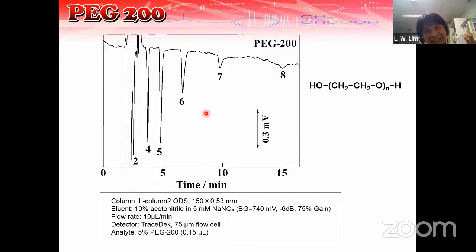So in this case, you have to find out what is the problem. And most of the time, you can solve the problem by washing your column, yeah? Because the main thing, the heart, you know, is the column. So when the column is contaminated, or sometimes with some absorptions, sometimes you will cause some bad result. So most of the time you can solve it by washing the system. You can wash not only the compounds, you can also wash some small rubbish. Sometimes there's some small rubbish inside. You have to wash it.